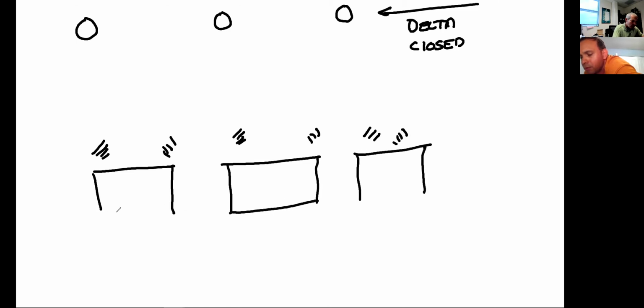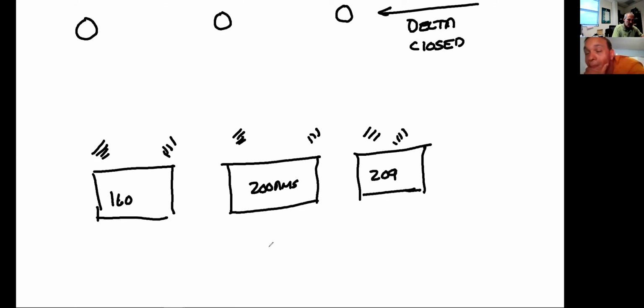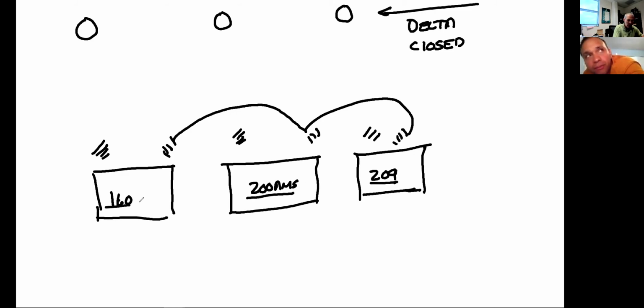Okay, let's talk a little bit about loads here. Say I've got on this transformer 200 amps being drawn, on this one 160, and on this one 209 -- just by the connection going on inside the place of business. Remember, I'm floating the neutral. When I have my neutral connected in the regular world, are these balanced for starters? 200 amps and 209, they're not balanced, okay?